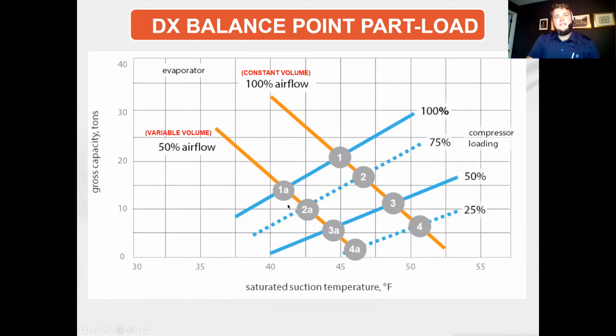Yeah, so just getting back to that and closing it off here a little bit, most of us don't even consider where our system might operate or go to this length as to what it might do at different variations of part load performance. But as we can see, this system as a connected design will live here for 95% of the time, right? Our design conditions can be down to 0.4% ASHRAE. So it's really a worthwhile exercise to do the cross plot, make sure that you're designing it as a connected system, and taking into consideration what happens in some of these part load cases, especially on a VAV.